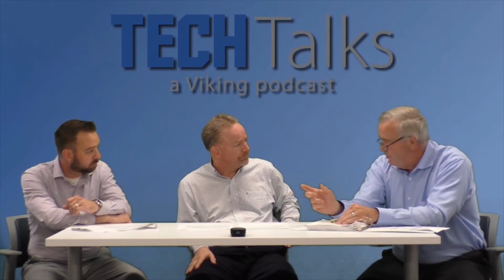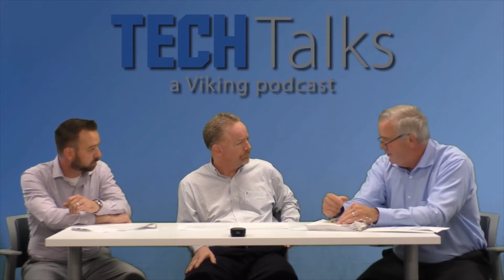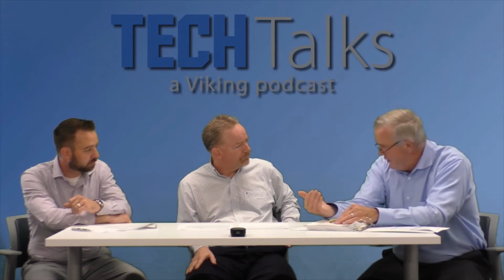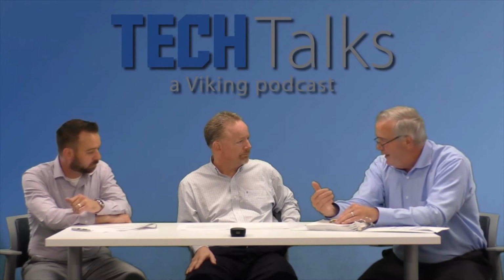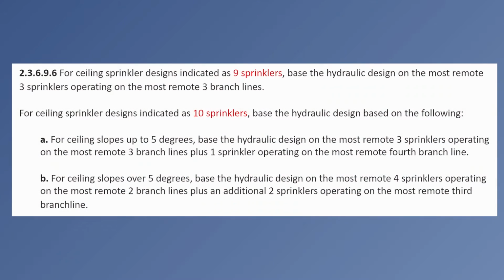Section 2.3.6.9.6 is specific to Table 17B, which says there are two design protocols in this table. One is 9 and one is 10, and here's how you calculate both of them. So for ceiling slopes up to, or independent of ceiling slope, up to 5 and I assume up to 2 in 12, it is a design for 9 sprinklers of 3 by 3, period. That doesn't change. It's across the board, so it's 3 by 3, you know what it is, and it's specific in 2.3.6.9.6.